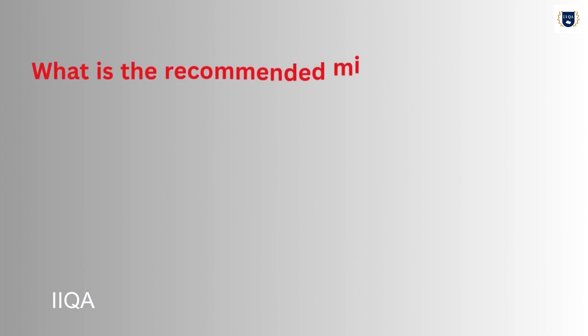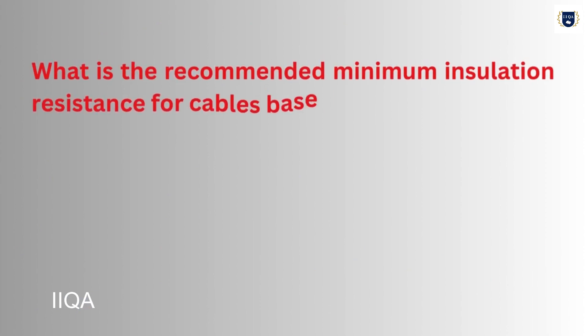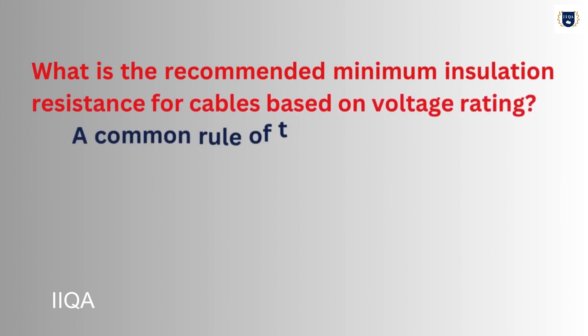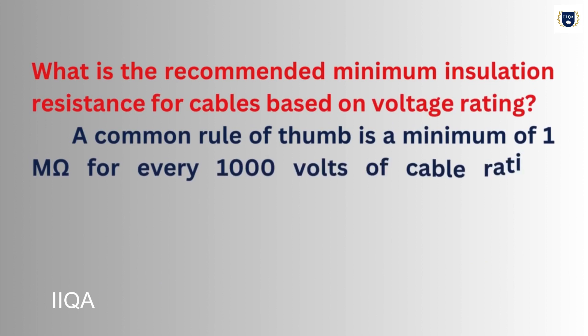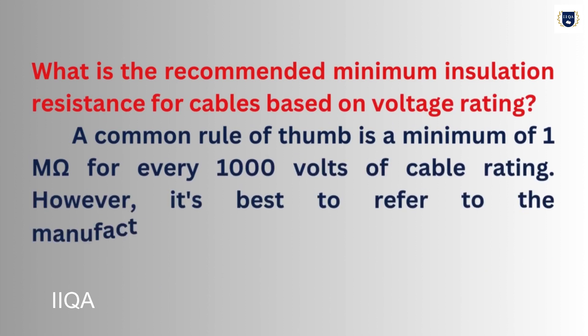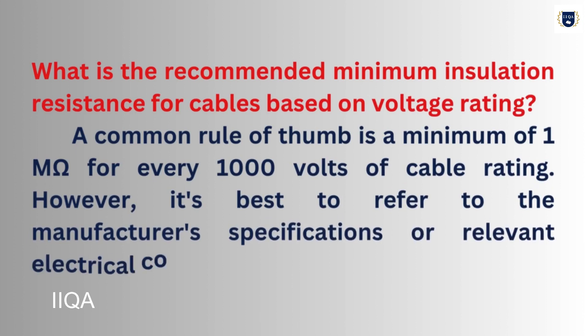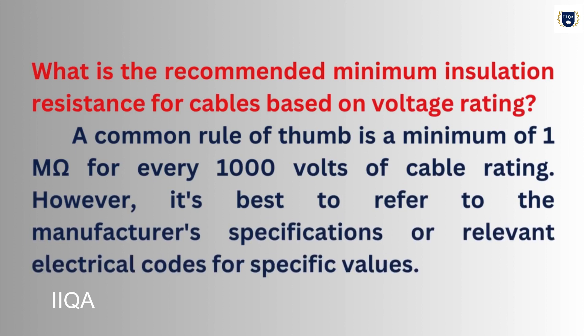What is the recommended minimum insulation resistance for cables based on voltage rating? A common rule of thumb is a minimum of 1 megohm for every 1000 volts of cable rating. However, it's best to refer to the manufacturer's specifications or relevant electrical codes for specific values.